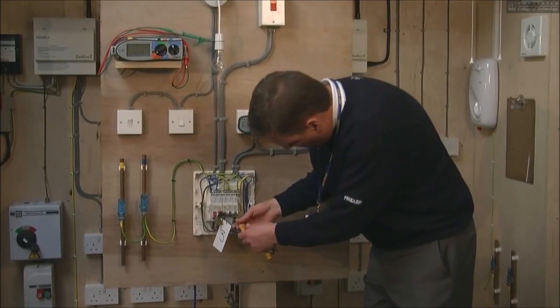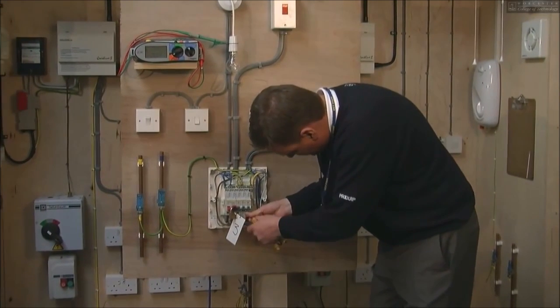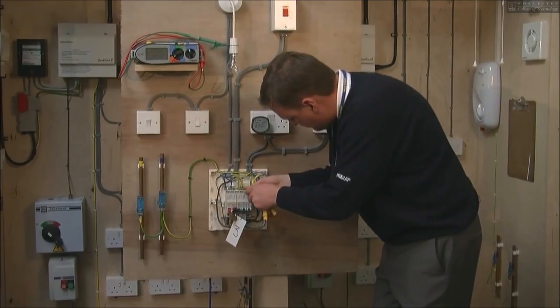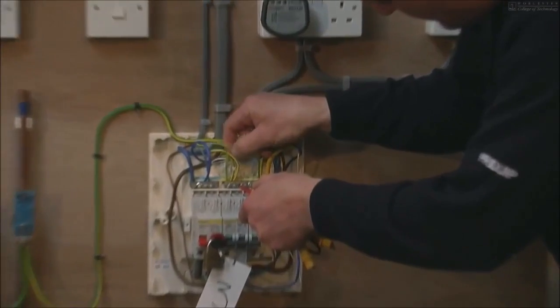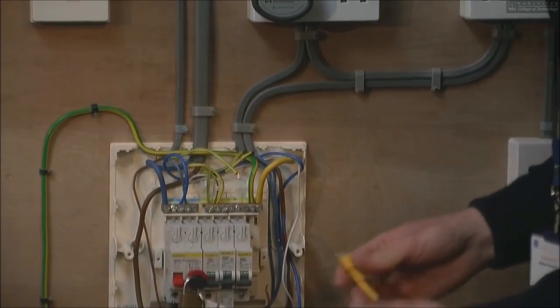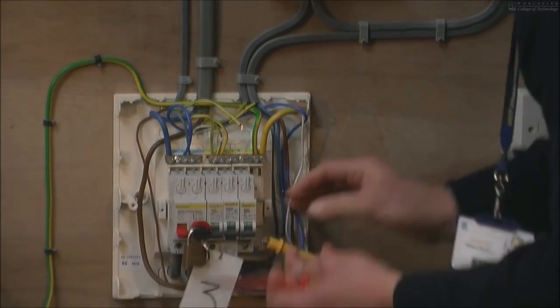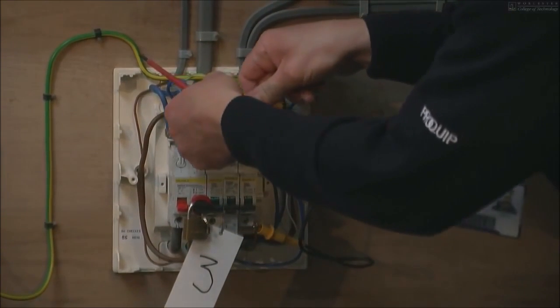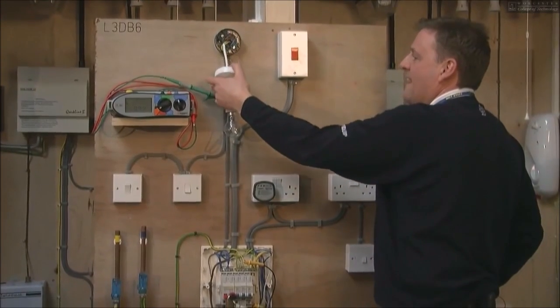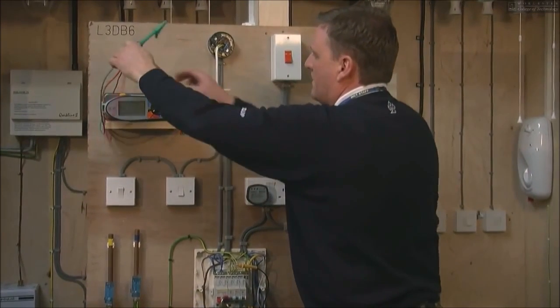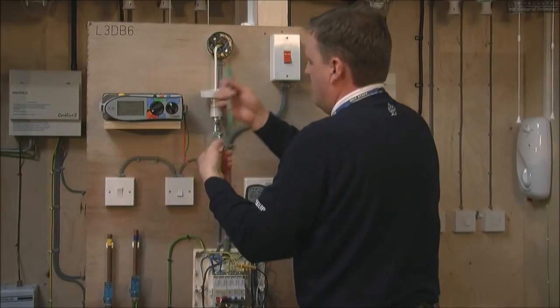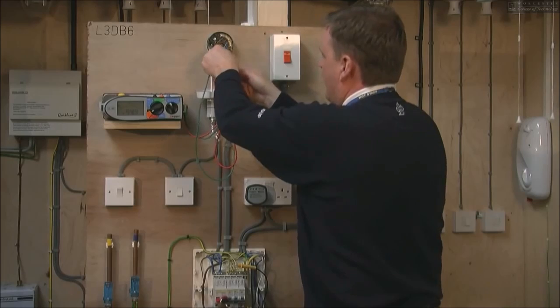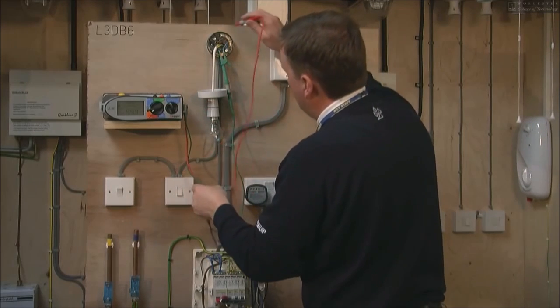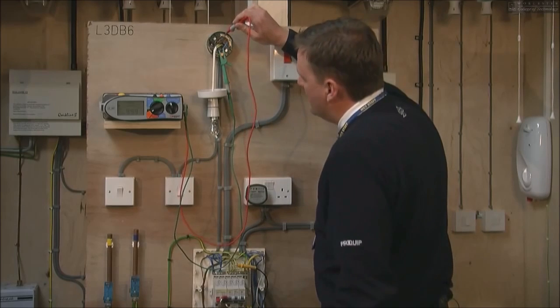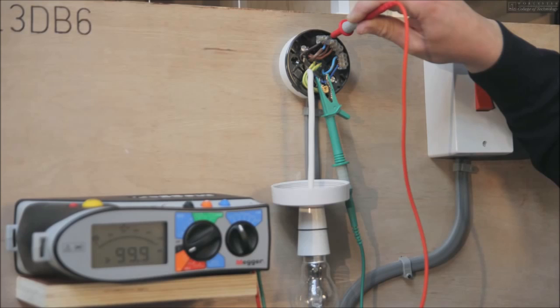We're going to move on to this final one here for the continuity. Simply undo the lighting conductor, a lighting earth cable. Again, place my little clips onto the cables, and unscrew the pendant like so. Clipping onto the earth bar inside like so. And if you look closely enough, you can see that I'm going onto the switch wire side of the circuit.